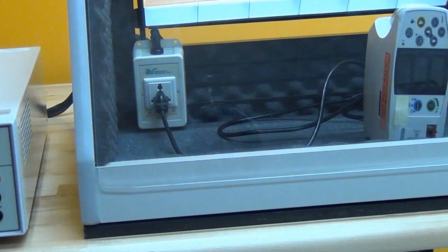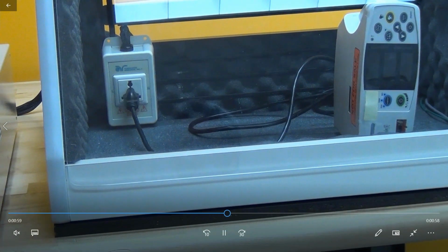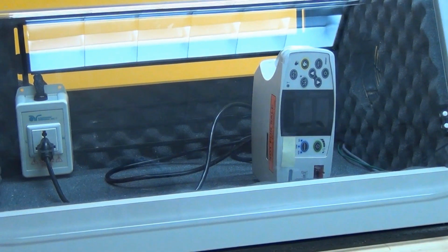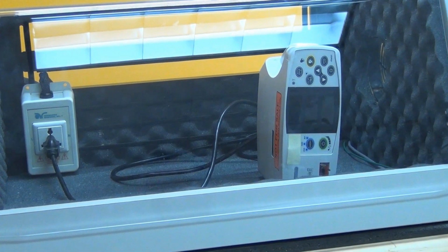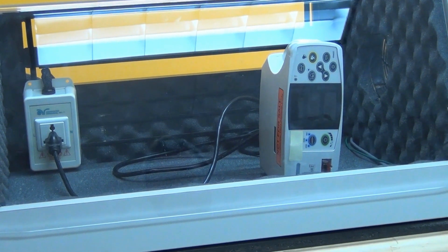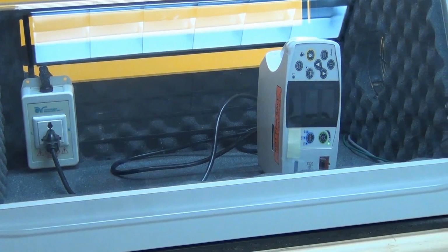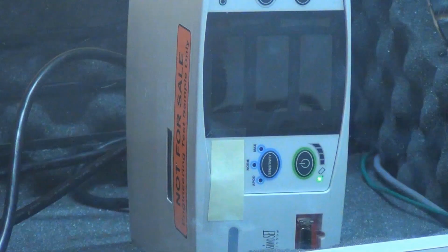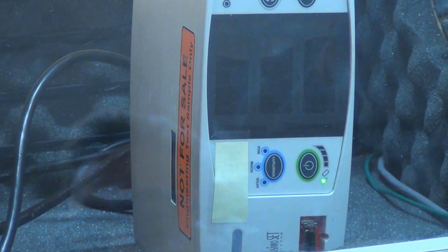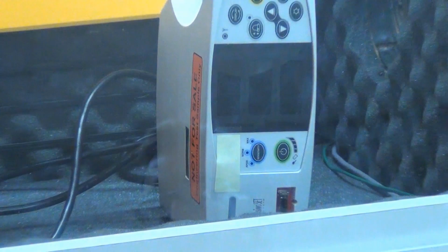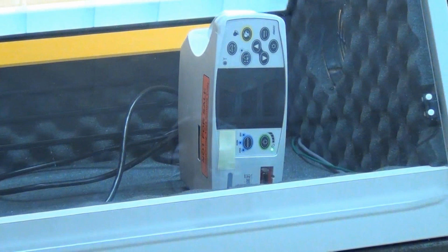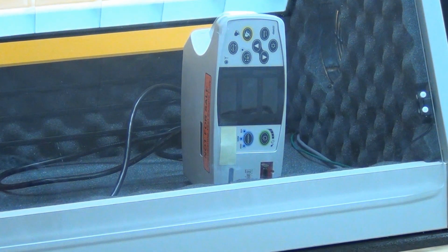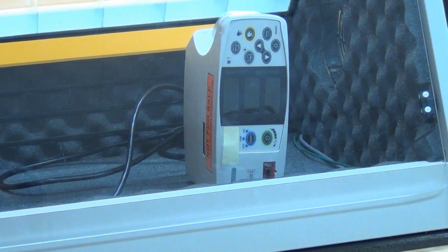And focusing back on our device under test, we're going to run this test one more time to show you that the device actually powers on, or at least it gets the auxiliary power. And obviously, in some cases, it is required per the standard to push the main power button on the device to the on position. But as you can see, the green LED at the bottom is turning on, which shows us that there's power coming to this device and the circuit inside it is being energized.